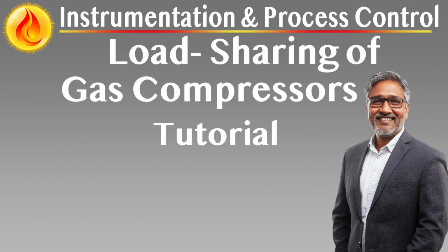Functional responses in load sharing mode. Primary capacity response. When net throughput must increase, load sharing controllers raise compressor speed or open flow paths in sync with the station controller's set point. During required reductions in flow, anti-surge controllers take over, adjusting recycle valves to reduce net capacity while maintaining surge protection. This dual-role strategy ensures that no compressor alone bears the burden of flow modulation.